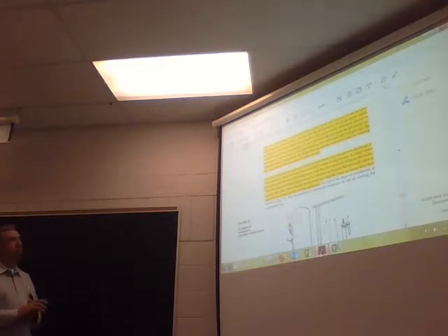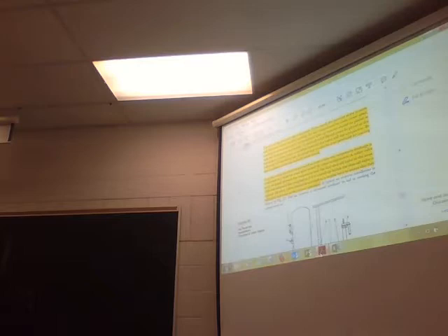A similar safeguard must be provided in the case where the compressor discharges to a connection to a large air main, also served by other compressors. A safety valve must be fitted between the compressor and the first shutoff valve in the main. So if we've got a main header, we've got 3 or 4 compressors tied into it, you must have a safety valve between that compressor and the main shutoff valve.